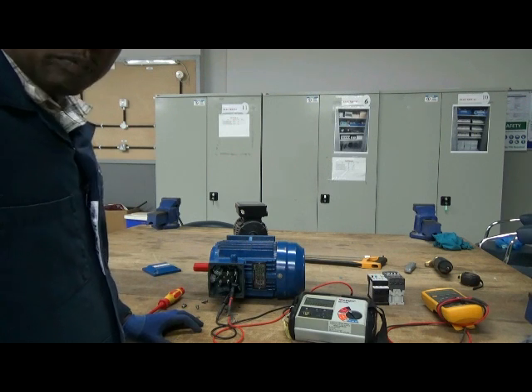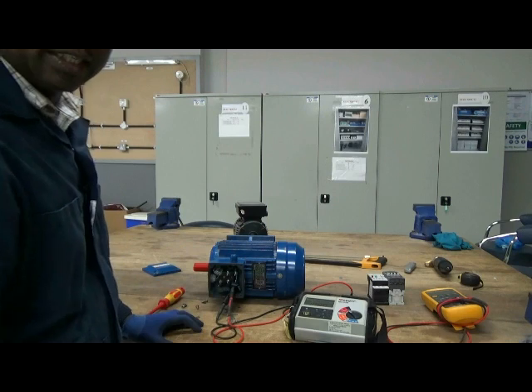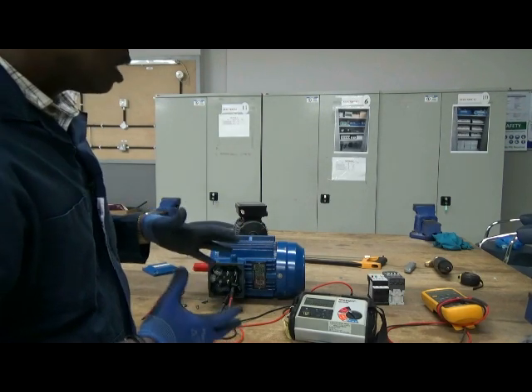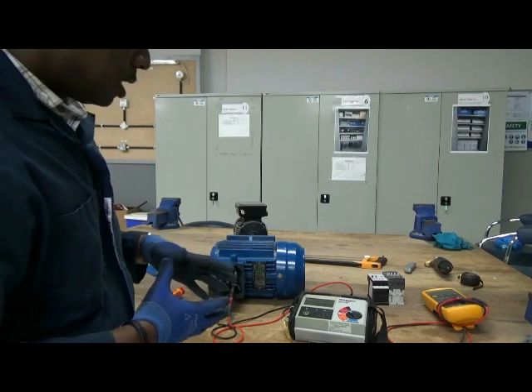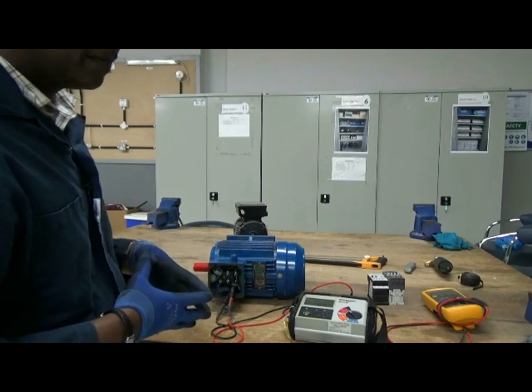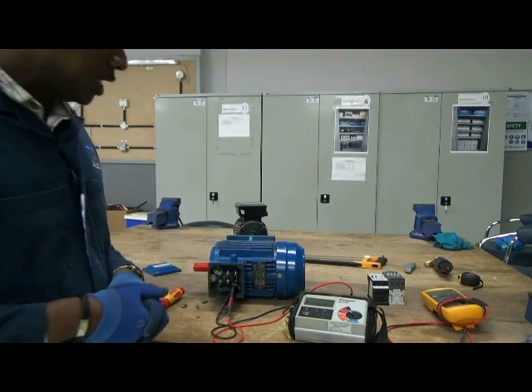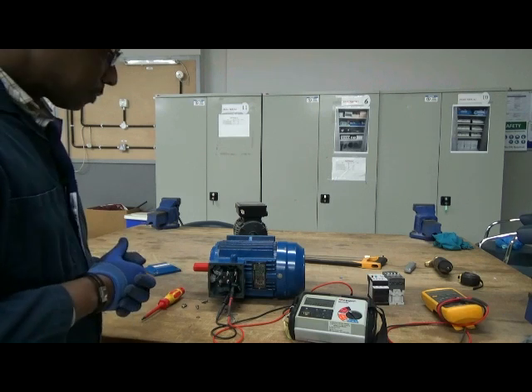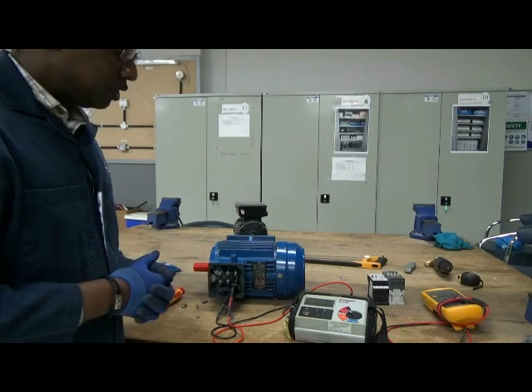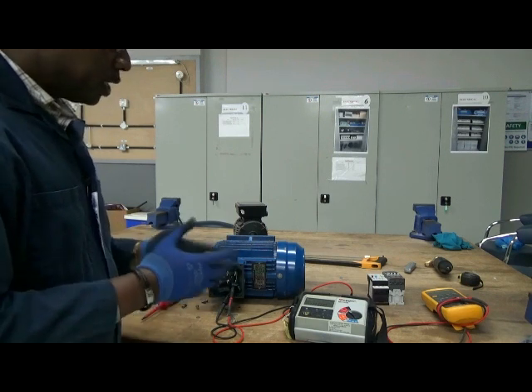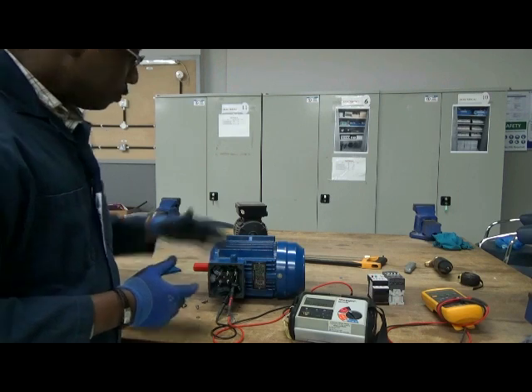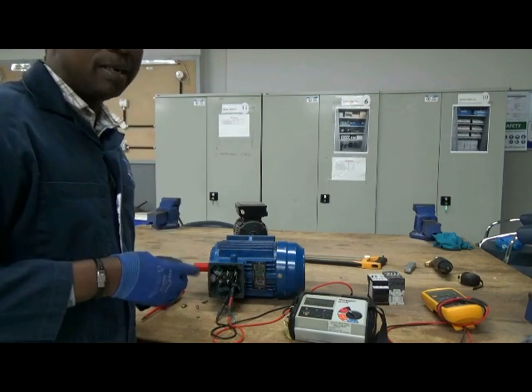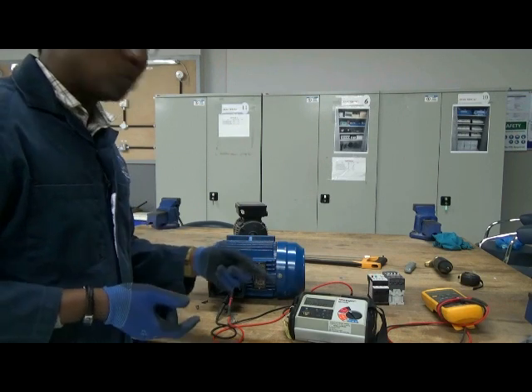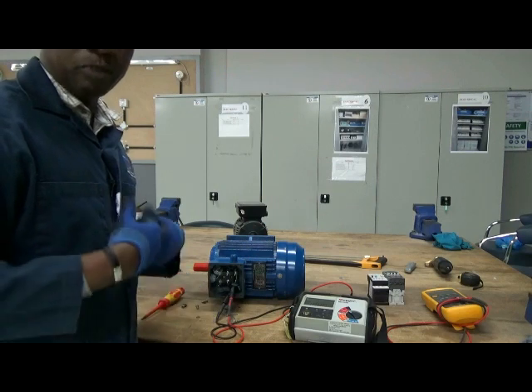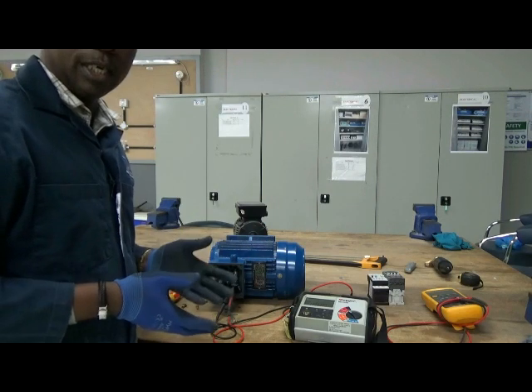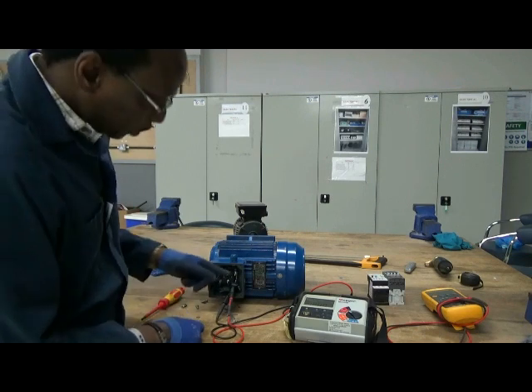Definitely current would not be able to pass from one point to the next, because there's a very, very high resistance. 1,000 mega ohms means 1,000 million ohms. That's very, very high resistance. And again, if we go back to our IET regulations, they stipulate that the minimum acceptable resistance for an insulation resistance test for such equipment should not be less than 1 mega ohm, 1 million ohms. But this one is giving me 1,000 mega ohms, which is very good, almost perfect, not really perfect, but very good. So that's acceptable, the resistance between that winding and the next one.